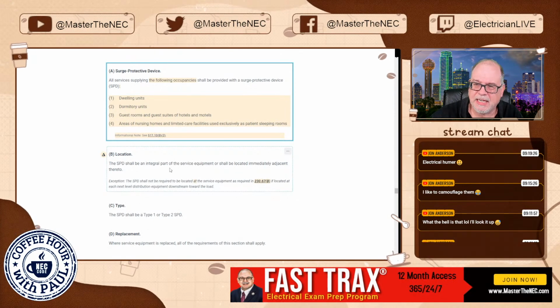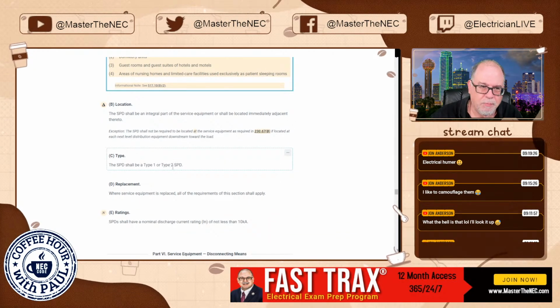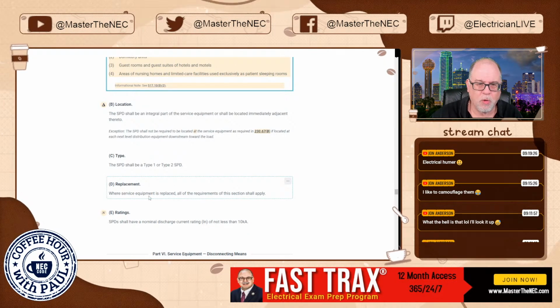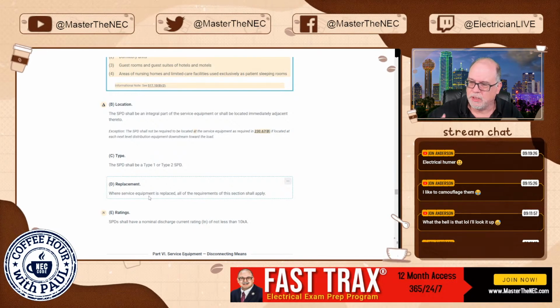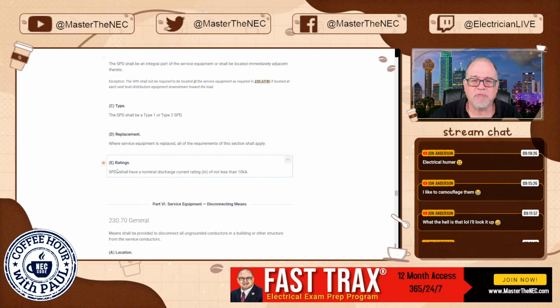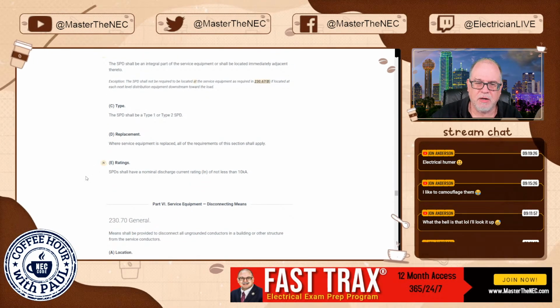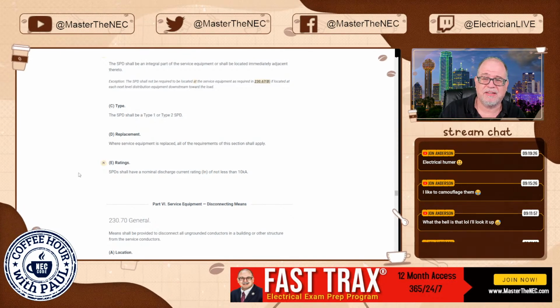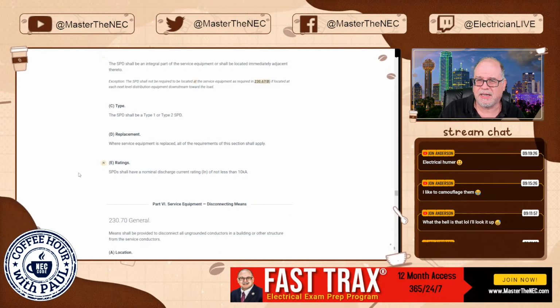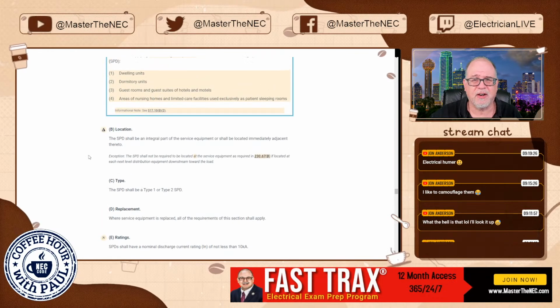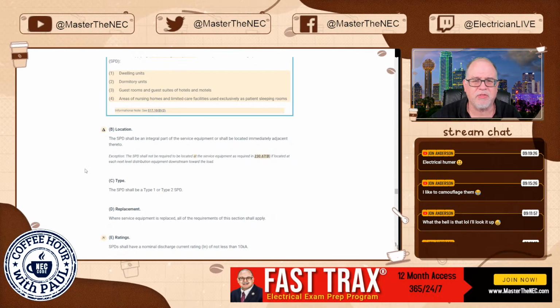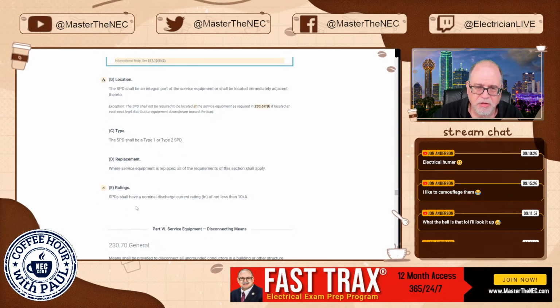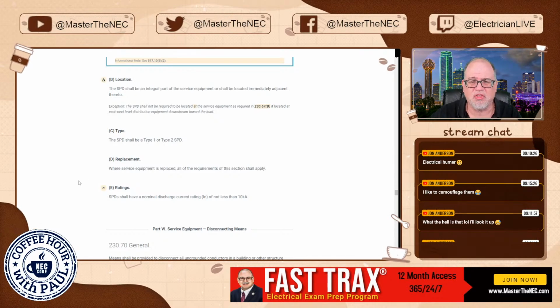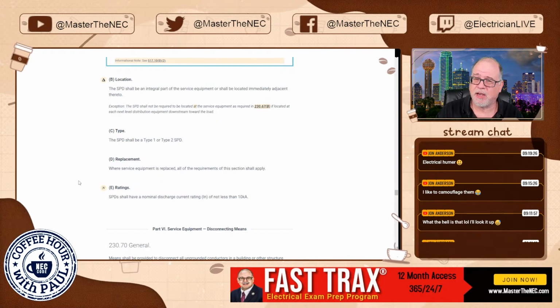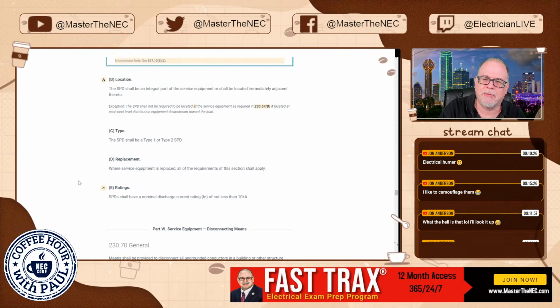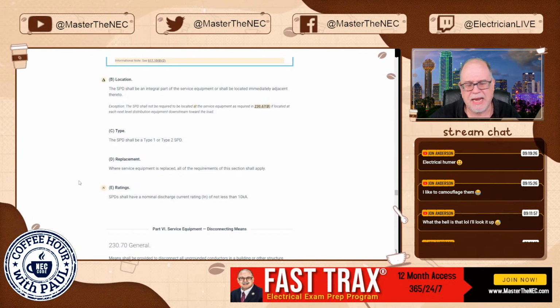So you've got your locations, same as before. Types, type 1, type 2, same as before. Replacement, same as before. If you do a service change, then this is now a retroactive rule. You're going to have to add SPDs. Ratings is new, which you saw on the feeder. It makes sense here. Typically, for one and two family, the utility is usually going to limit you to 10,000 amps of available fault current anyway. But since this is much broader now, covering dormitory units, guest rooms and guest suites, hotels and motels, where there are services involved, you're not dealing with just dwellings, so you need to pay attention to those SPDs. The manufacturer should take care of this for you, hopefully, but at least you know that it has to have a nominal discharge current rating of not less than 10,000 amps, or 10 kA.